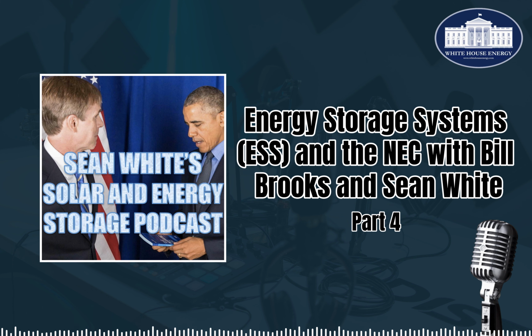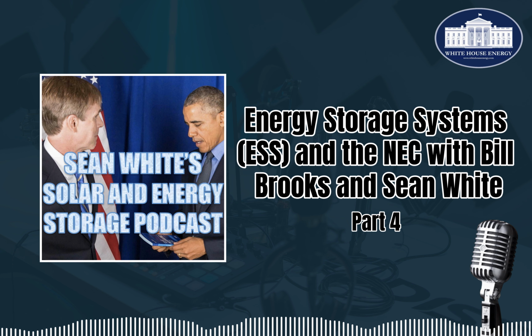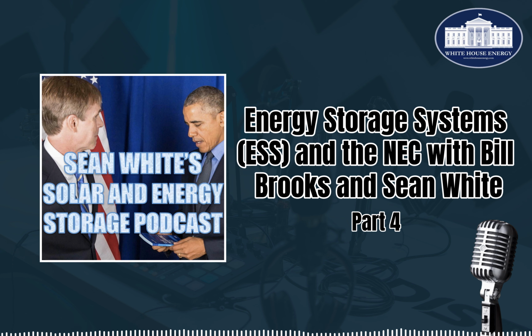The sum rules, so we just go 20, 40, 60, 80, 100. We don't even have to look to see if it's solar or load breakers. And we don't really have to pay attention to the main breaker. I even think, why even have a main breaker? Because we're protecting everything in reverse. If you have 100 amps of breakers, there's never going to be more than 100 amps coming out of there. Doesn't have to be at any certain side of the bus bar or anything like that.